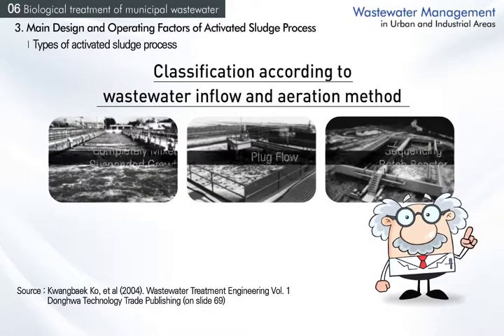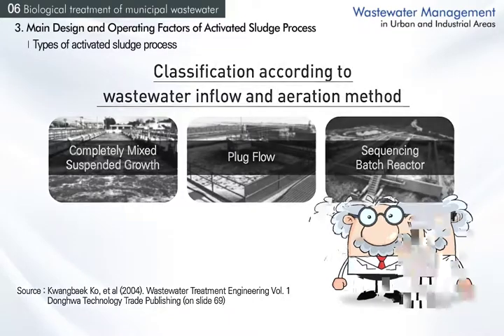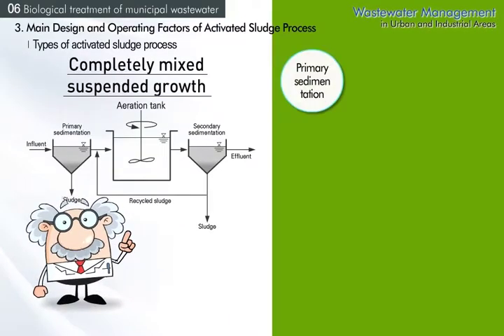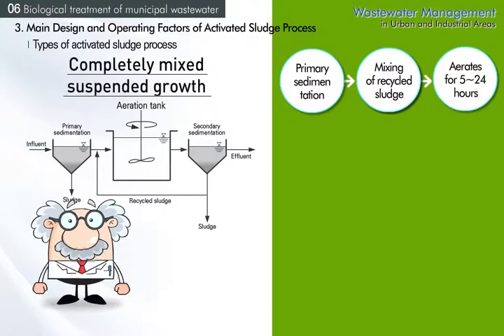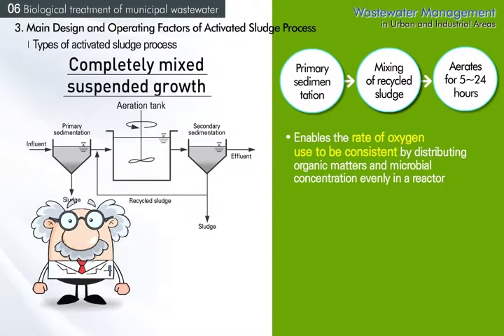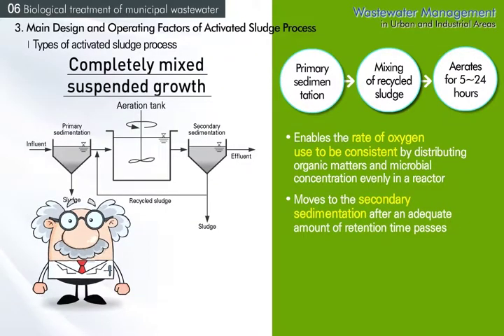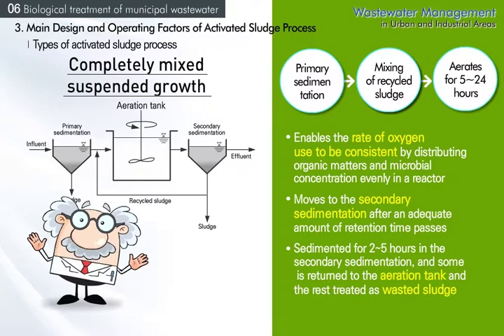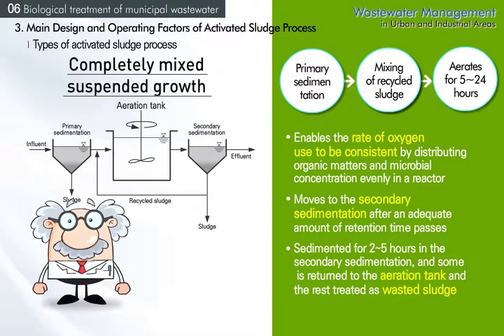Activated sludge process can be divided into completely mixed suspended growth, plug flow, and sequencing batch reactor depending on wastewater inflow and aeration. In completely mixed suspended growth, wastewater after primary sedimentation is completely mixed with recycled sludge in an aeration tank, aerated for 5 to 24 hours so that concentration of organic matters and microorganisms are distributed evenly. The oxygen use rate is consistent regardless of reactor location. After adequate retention time, the mixed liquor is transferred to secondary sedimentation for 2 to 5 hours, then sedimented sludge is partly returned as recycled sludge and the rest sent to sludge treatment as wasted sludge.